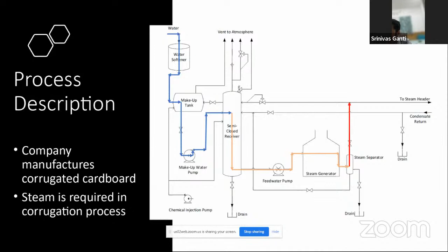Once it goes to the semi-closed vessel, it has a connection from the steam header based on pressure control, as well as condensate return. So it is quite preheated in this case. We can see that. And the preheated makeup water will go through the feed water pump to a steam generator. From there, it will go to a steam separator, where the condensable liquids above saturation will come out from the drain, and the saturated steam will go to the head of our corrugation process.